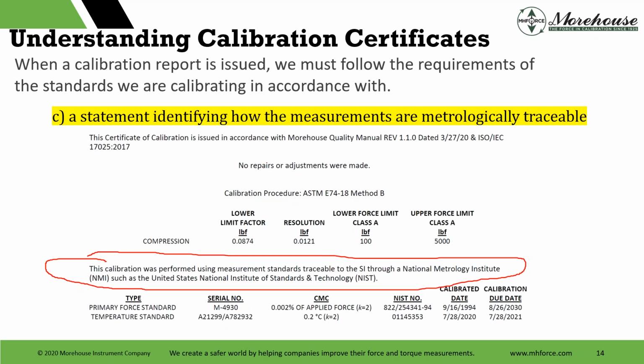And when calibrating load cells, many laboratories fail to get metrological aspects correct and improperly state NIST traceable master standards. That is wrong. Or traceability to NIST, which is wrong. At Morehouse, we have seen all sorts of incorrect usage of NIST traceability. I bought a torque wrench off of Amazon one time, and I got a little piece of paper with it that said, this is traceable to NIST. Just a little tiny piece of paper, probably 2 inches high by 4 inches wide, and that's all that said on it. This serial number, blah, blah, blah, is traceable to NIST.